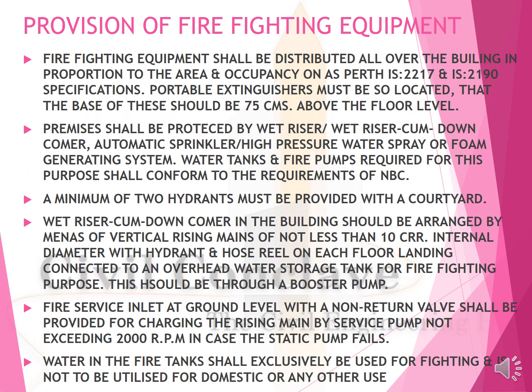Provision of the firefighting equipment. Fire equipment shall be distributed all over the building in accordance with IS 2217 and 2190. Premises shall be protected by a wet riser cum downcomer, automatic sprinkler, high pressure water spray or foam generating system. Water tanks and fire pumps required for this purpose shall conform to the requirements of the National Building Code. A minimum of 2 fire hydrants to be provided in the courtyard.